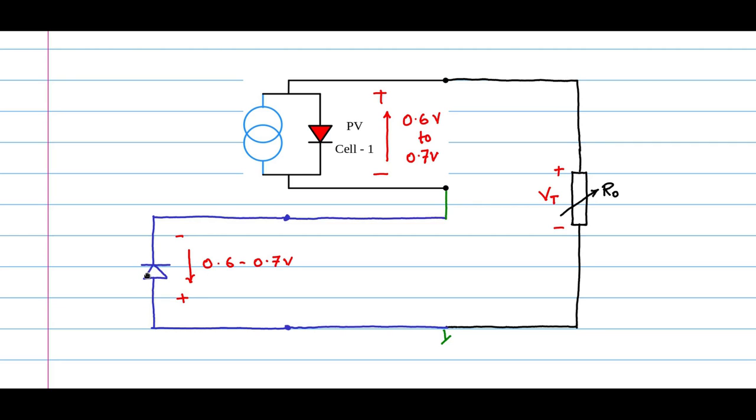That would make this diode more costly than the PV cell itself, so it is not a workable solution. The via media, that in-between solution, is you put the bypass across a cluster of PV cells.